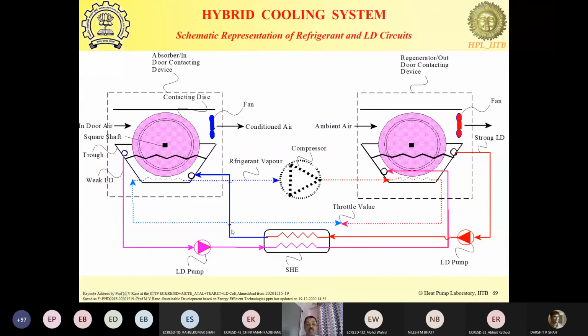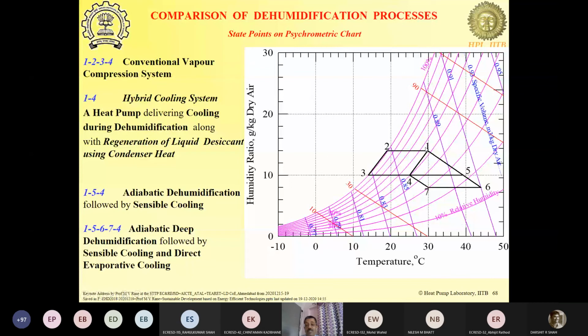So the refrigerant circuit and the liquid desiccant circuit are integrated using our diabatic contacting device. So the cooled liquid desiccant is dehumidifying and cooling the air in a single step, right from here to here, instead of going all the way like this. You can go from here to here, and you can see that the minimum temperature is much higher, so our evaporator can be much higher. Here the minimum temperature was here, so our evaporator was typically 7.2 degrees here.